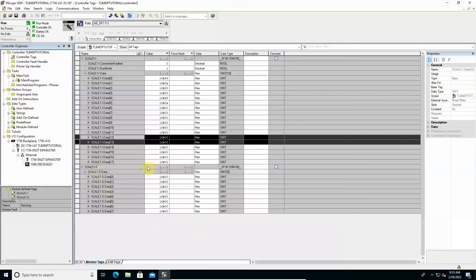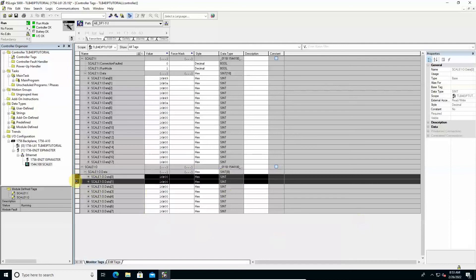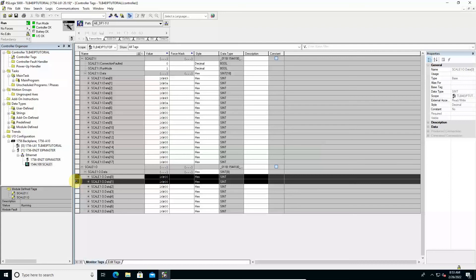Among the data output from the PLC, it is useful to focus especially on the command register field. This 2-byte value is used to send specific numeric codes to the instrument, each of which corresponds to a request for execution of a specific operation. All the numerical codes allowed and the relative associated operations are available in the protocol's manual.